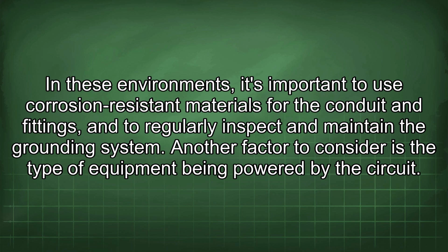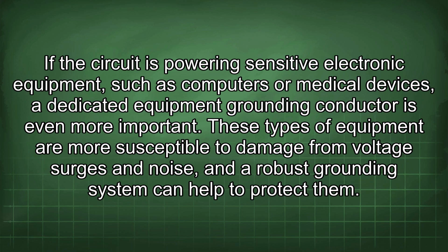Another factor to consider is the type of equipment being powered by the circuit. If the circuit is powering sensitive electronic equipment, such as computers or medical devices, a dedicated equipment grounding conductor is even more important. These types of equipment are more susceptible to damage from voltage surges and noise, and a robust grounding system can help to protect them.